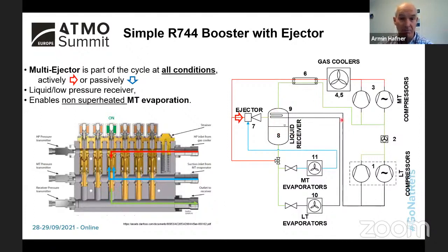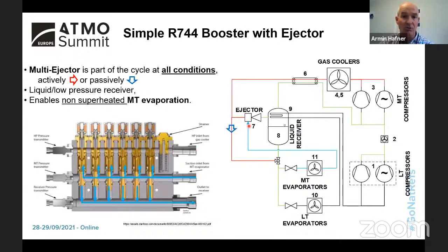So that is the pressure level the compressor sees, while traditionally the compressor would control the pressure level in the MT evaporators, but in this case, it's just controlling the pressure in the liquid receiver, the low pressure receiver, which is slightly higher. As long as the ejector can bring all the vapor from the MT evaporators back into the receiver, everything is fine. At lower ambient temperatures, the ability to pump is going down, and in this case, the ejector is not utilized. We are just closing the port here, and the high side pressure is not distributed anymore through the ejector.